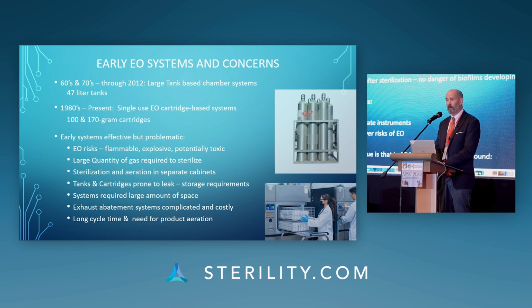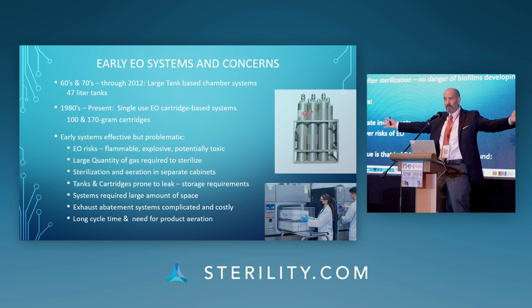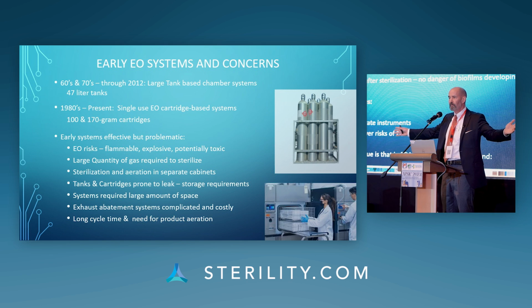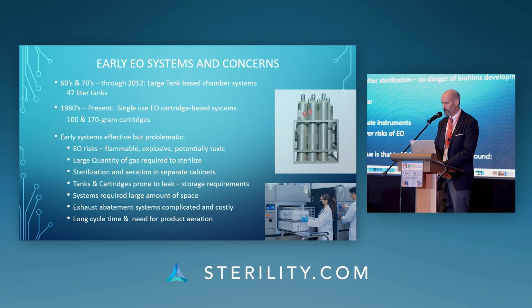The systems required a large amount of space. Many of you probably remember the old ethylene oxide systems that were literally built into a wall, and there was a service room behind the sterilizers that had the air compressors and water lines and vacuum lines. Finally, when emissions abatement equipment is required, these systems use so much gas that scrubbing the gas, removing the gas from the exhaust, can be complicated and expensive.